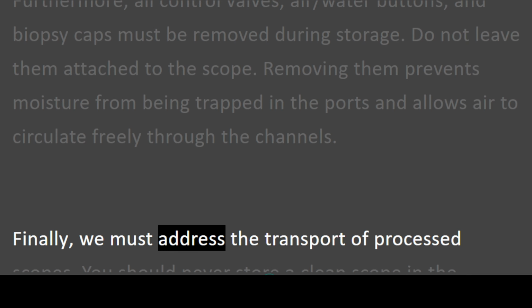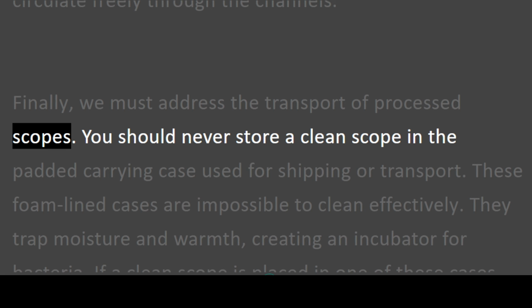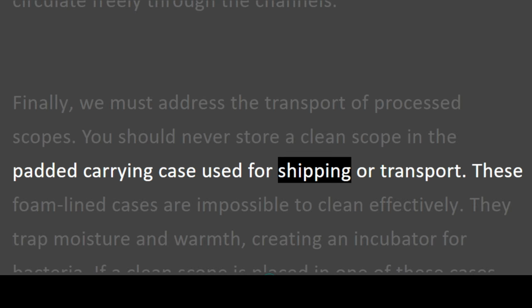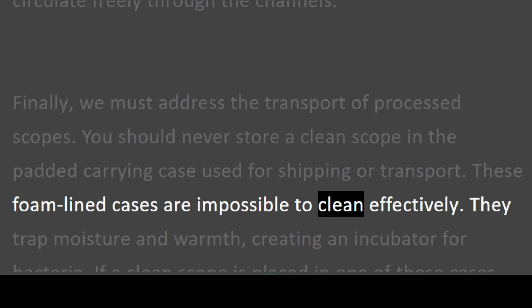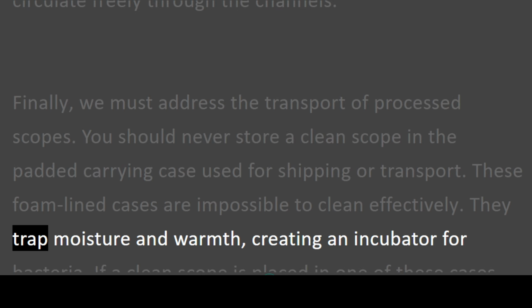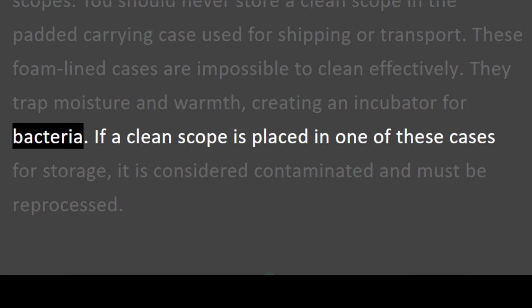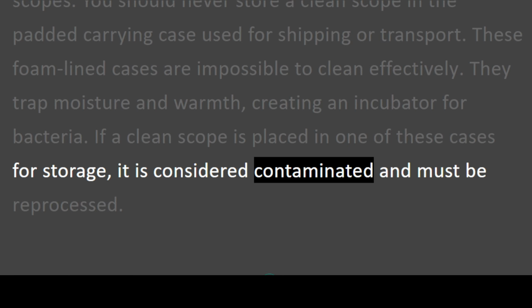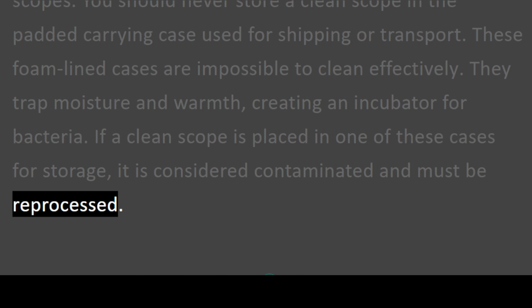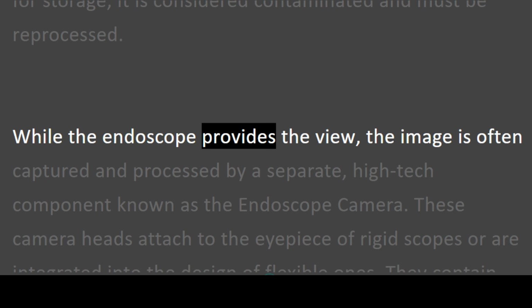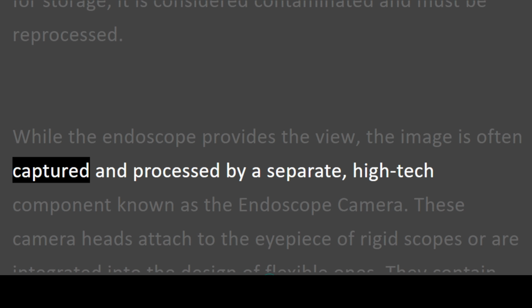Finally, we must address the transport of processed scopes. You should never store a clean scope in the padded carrying case used for shipping or transport. These foam-lined cases are impossible to clean effectively. They trap moisture and warmth, creating an incubator for bacteria. If a clean scope is placed in one of these cases for storage, it is considered contaminated and must be reprocessed.